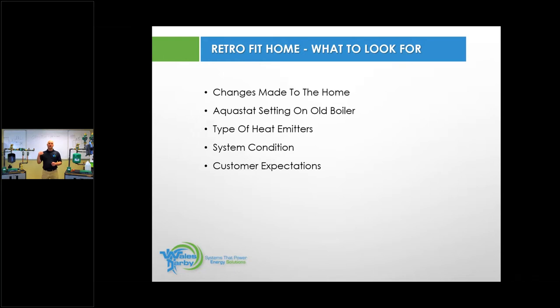And again, that homeowner has expectations when you come in there to give them a proposal. If they've got creaking on the third floor, changing out the boiler is probably not going to fix that creaking on the third floor. But in their mind, they think it will. Oh, I'm changing the boiler, everything's going to be fixed. Not necessarily the case. So just make sure you have that conversation with the homeowner, everything working okay. If you have an existing boiler in the home now, it's always a good idea to run that in a full operation mode and just watch it run, function, and listen to it. And make sure that when you give them a proposal to replace the boiler, you can meet all those expectations.